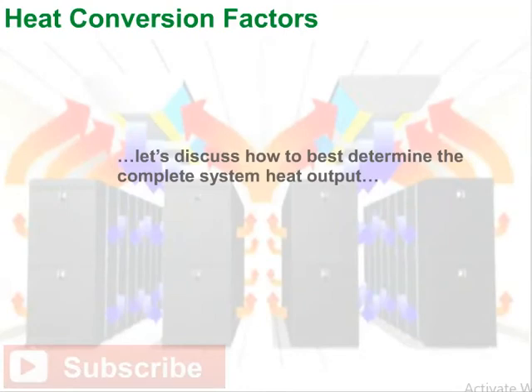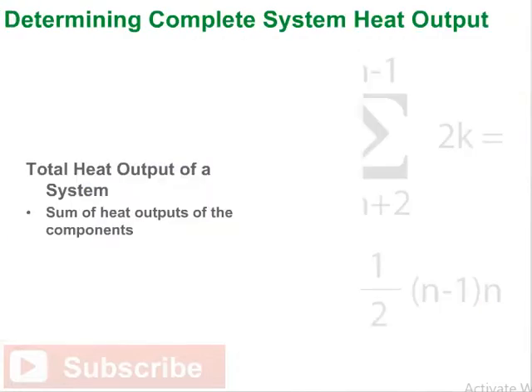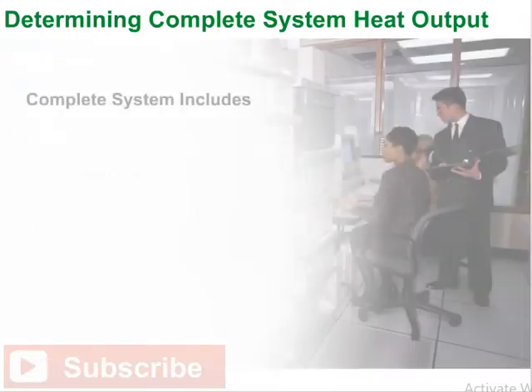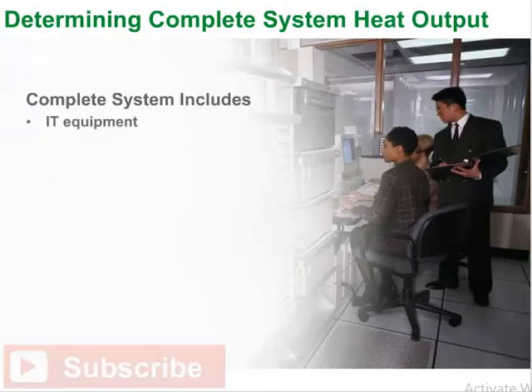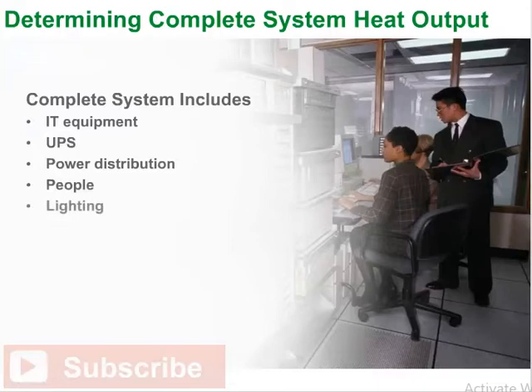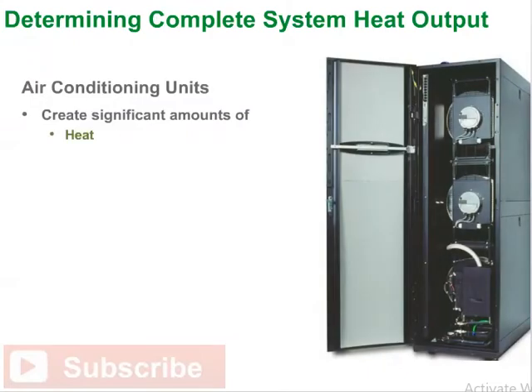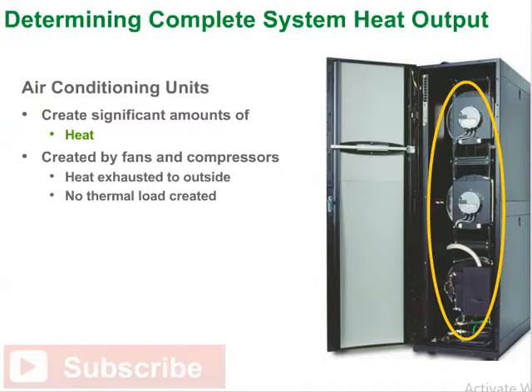Let's discuss how to best determine the complete system heat output. The total heat output of a system is the sum of the heat outputs of its components. The complete system includes the IT equipment plus other items such as UPS, power distribution, people, lighting, and air conditioning units. It's important to note that air conditioning units in the data center create a significant amount of heat from fans and compressors.